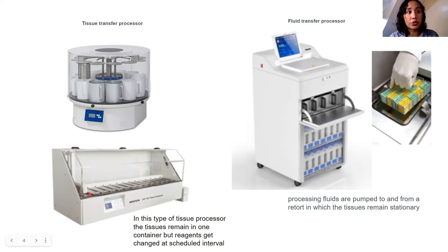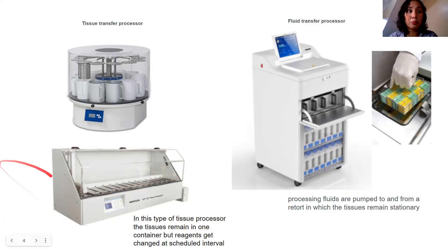The role of the medical technologist is to fill up the containers. First, fill it with formaldehyde; next, 70% alcohol, and so on. In manual processing, the human transfers the cassettes from one reagent to another. In the automatic processor, the machine moves the tissue. We have the horizontal type and the carousel type — the carousel type is more compact.